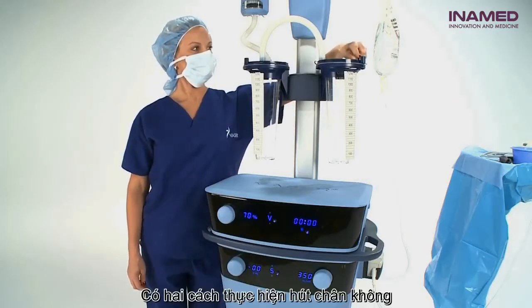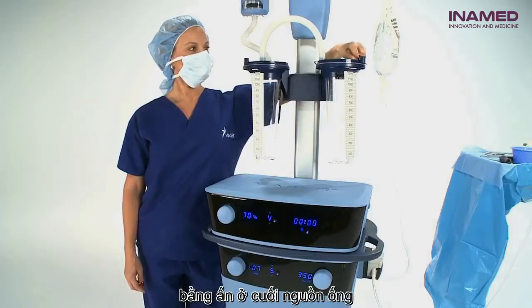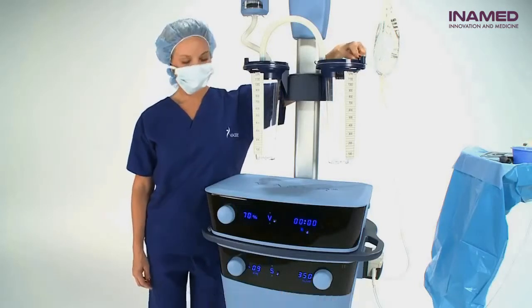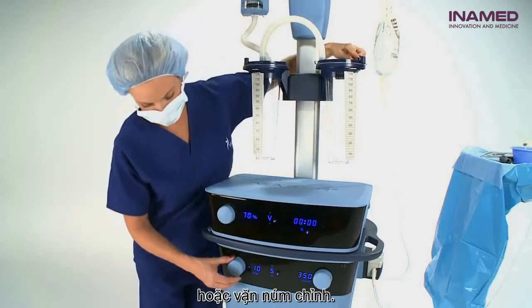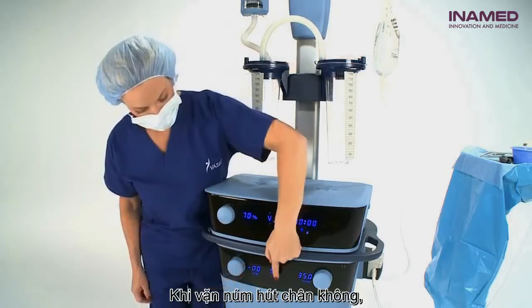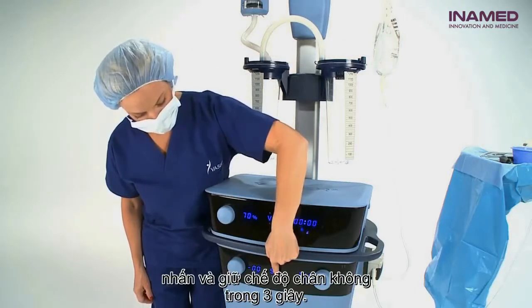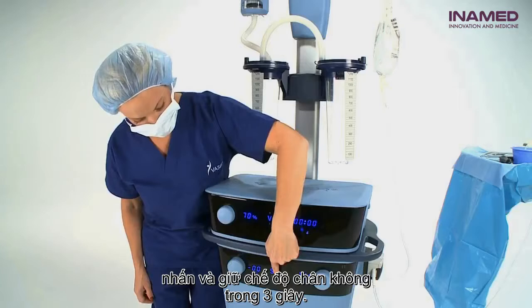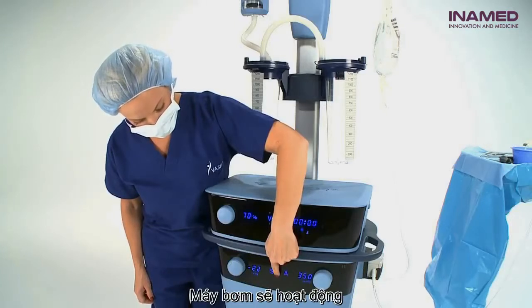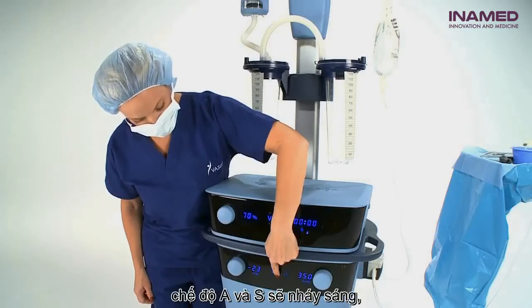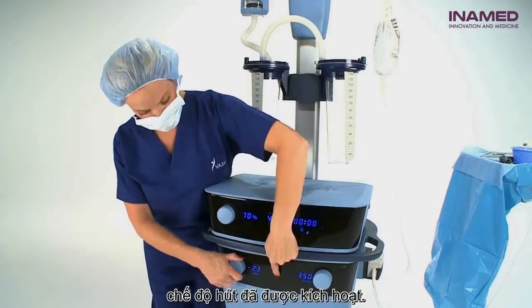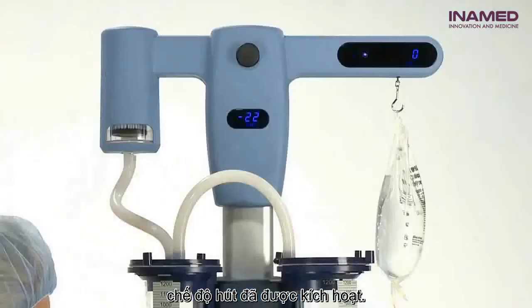There are two ways to occlude the vacuum, either by plugging the end of the suction source tubing or by engaging the occlude mode. To engage the occlude mode, press and hold the vacuum mode button for about 3 seconds. The pump will engage and the A and S will be flashing. This indicates that occlude mode is activated.